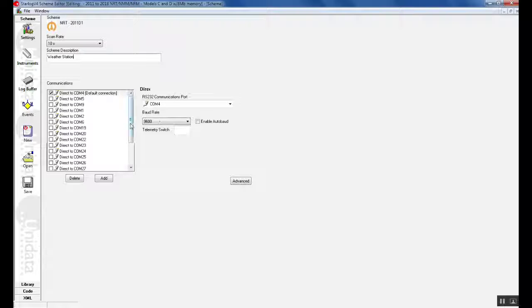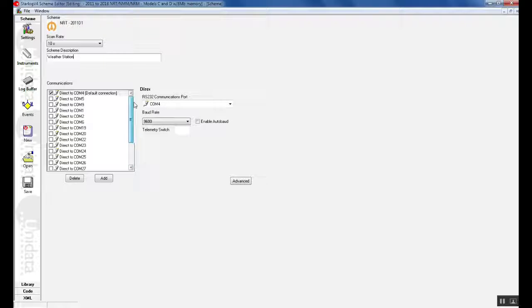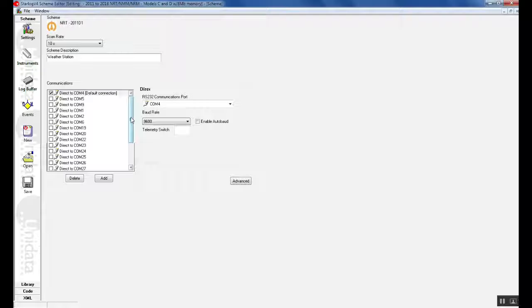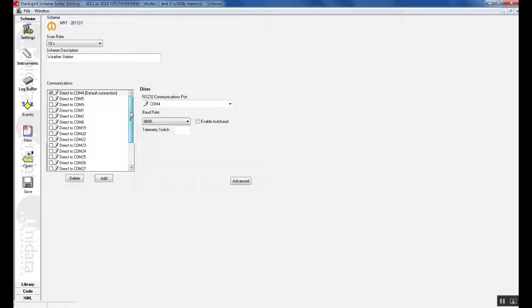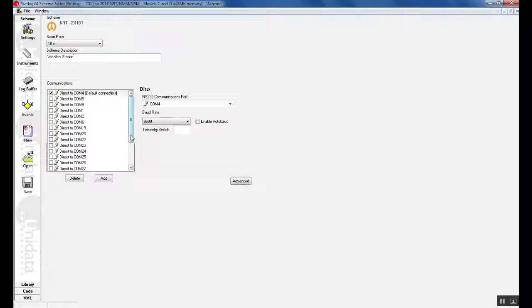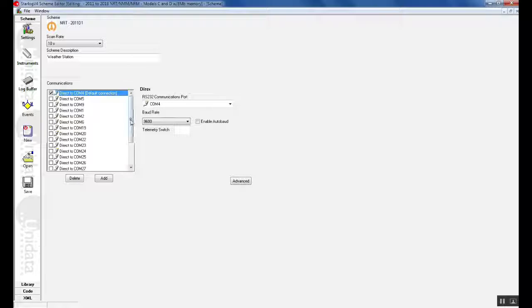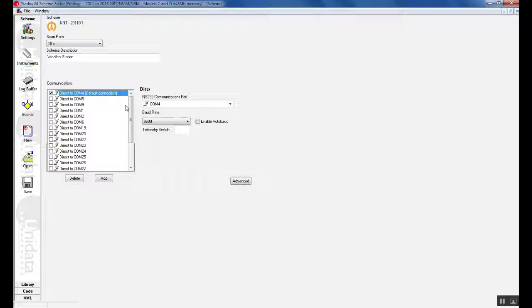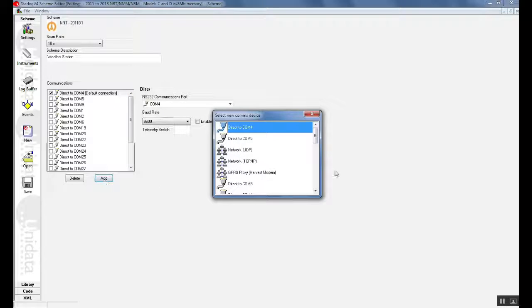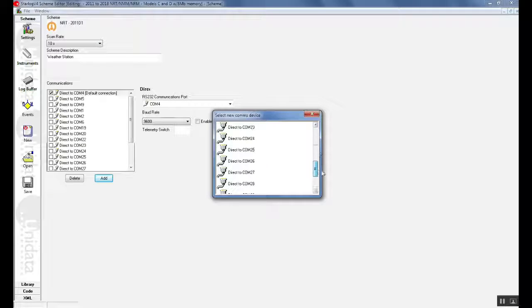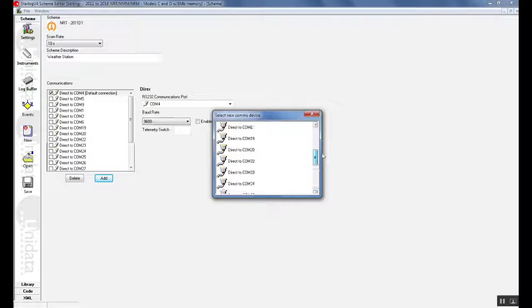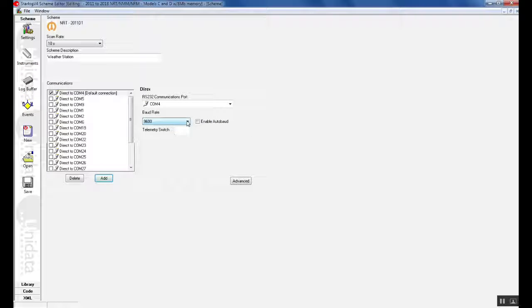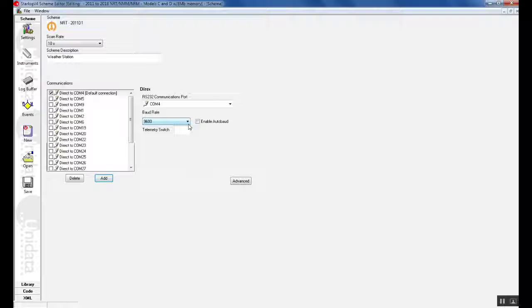In the communications box we also have the communications ports we will be connecting to. This can be found in the system parameters in device manager on your computer. Today we will be connecting to COM port 4 so we can select COM port 4 here. All the COM ports that are on the PC will be shown up in this window. If they are not shown up in this window we can click the add button and add a COM port that is on the PC. The standard baud rate on a NEON unit and all other Unidata loggers is 9600 baud so this can be kept as is.